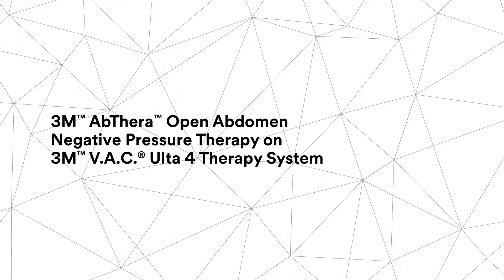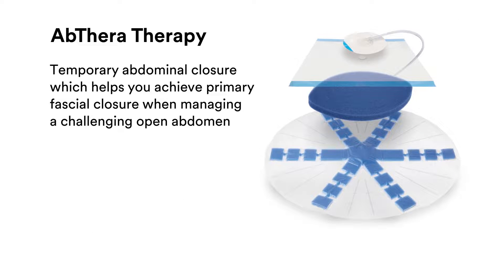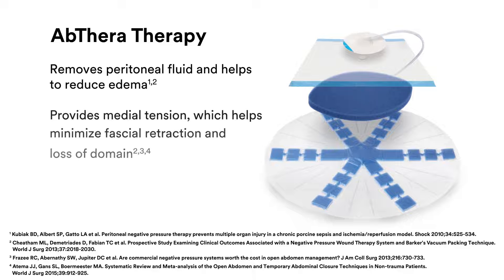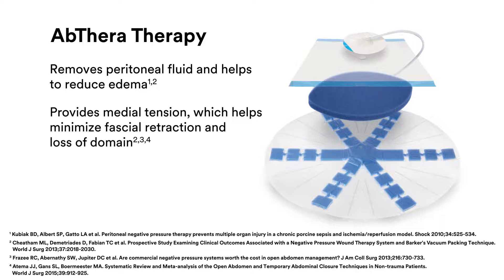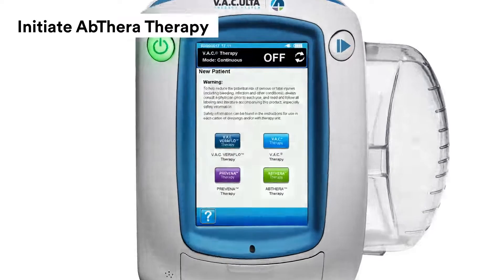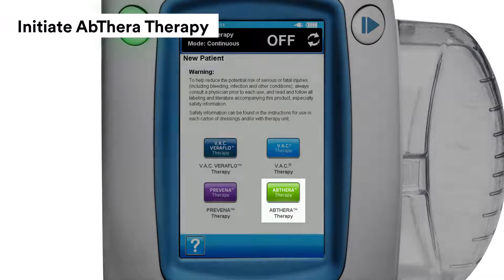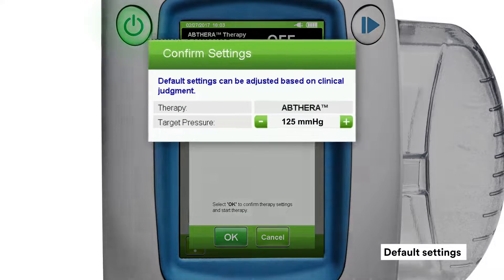3M AbThera open abdomen negative pressure therapy provides temporary abdominal closure, which helps you achieve primary fascial closure when managing a challenging open abdomen. AbThera therapy is designed to manage the open abdomen by removing peritoneal fluid and helping to reduce edema, providing medial tension which helps minimize fascial retraction and loss of domain. To initiate AbThera therapy, press the green AbThera therapy button. The confirm settings screen gives you an option for target pressure of 100 to 150 millimeters of mercury, which you can adjust using the plus and minus signs.